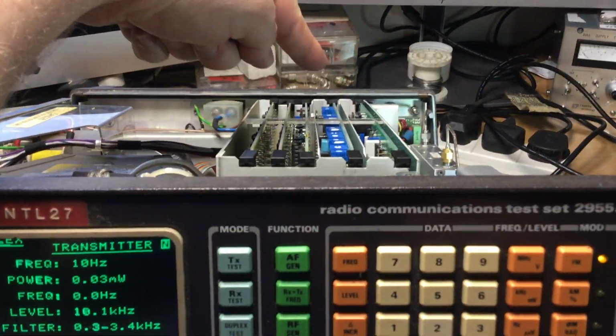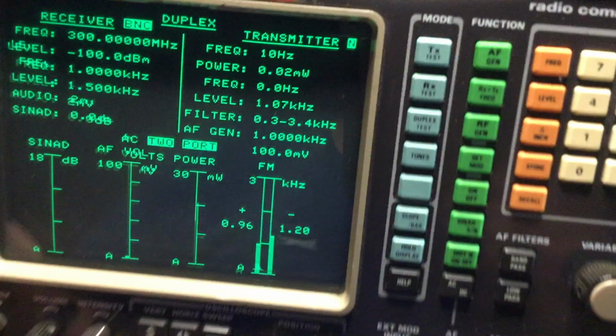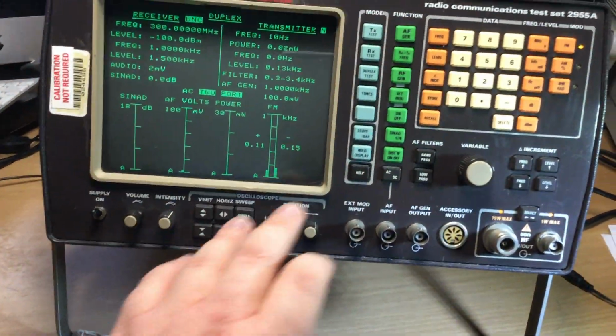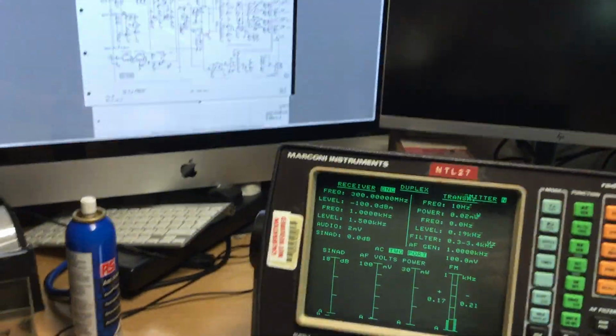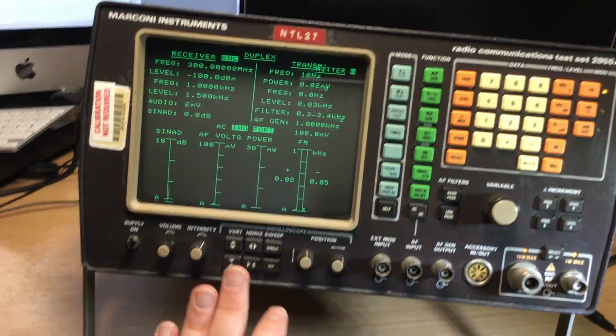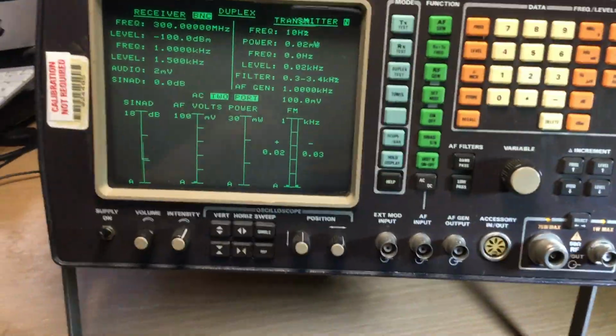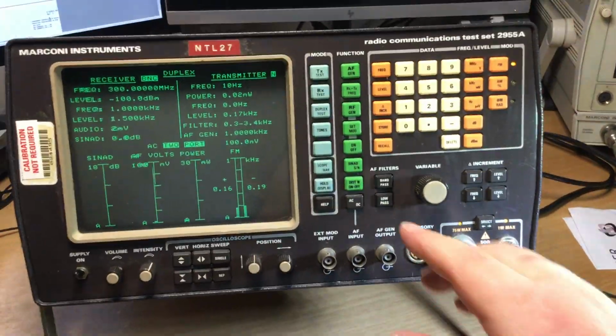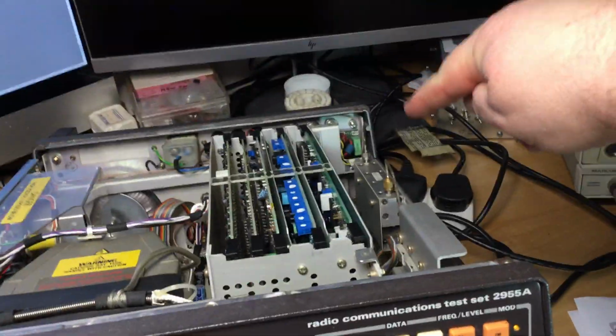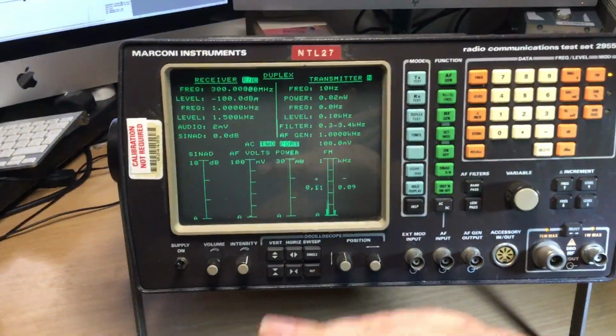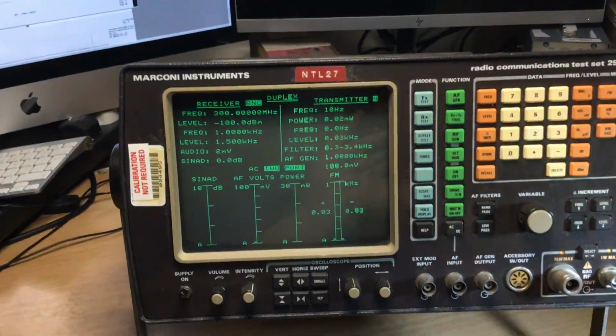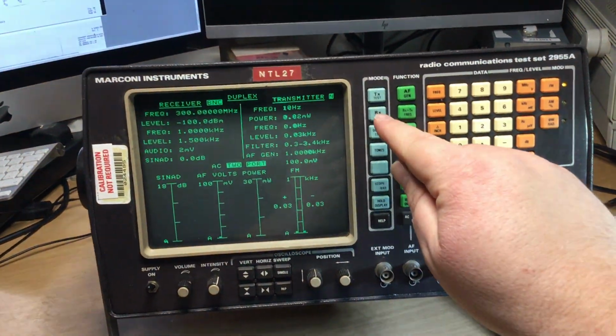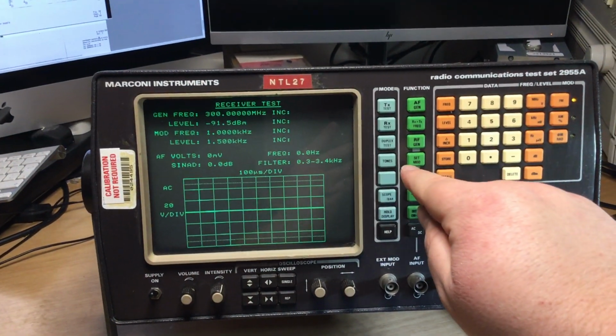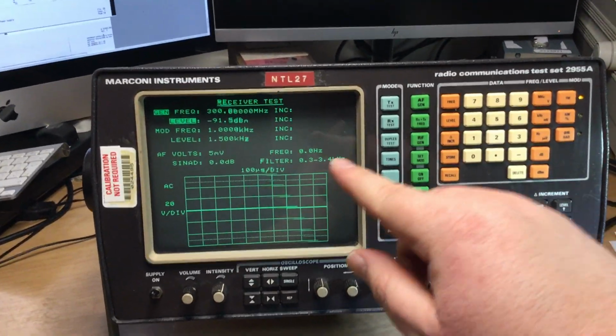And as I say, half of the instrument is calibrated using the potentiometers that's here, but also there is a code that you can enter in a particular sequence, which is in the service manual, that allows you to enter in the software calibration mode. Because obviously, as well as having the mechanical RF attenuator there, which is a step attenuator, so it's going in steps of attenuation, then we've got basically to also calibrate the RF level which is in between those steps.